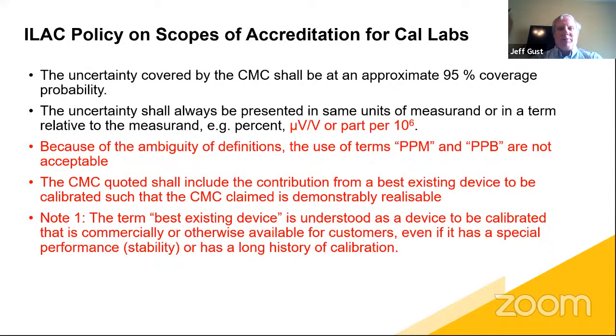However, when you're dealing with measurement uncertainty, you cannot have 4 digits of resolution, because that infers that you know your uncertainty down to 4 significant digits, and that just never happens. And again, my previous talk on that subject does a really nice historical breakdown about the difference between approximately 95%, which is meant to infer 2 sigma, versus exactly 95%, which is k equals 1.96. There is a difference between those two.